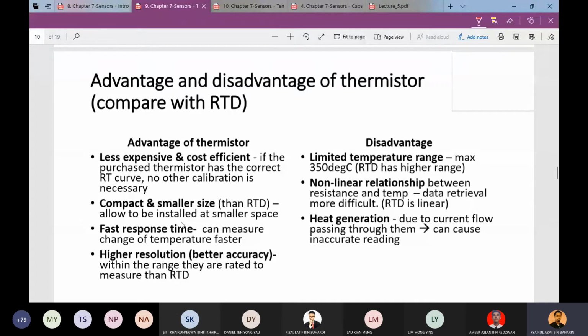And then fast response time, faster than RTD, dia lagi cepat. Bila berlaku perubahan suhu, dia boleh measure. And then higher resolution and better accuracy within the range they are rated to measure, compared to RTD. Maknanya range dia kurang berbanding platinum RTD, tapi resolution dia lagi sensitif, dia boleh baca skala yang kecil.